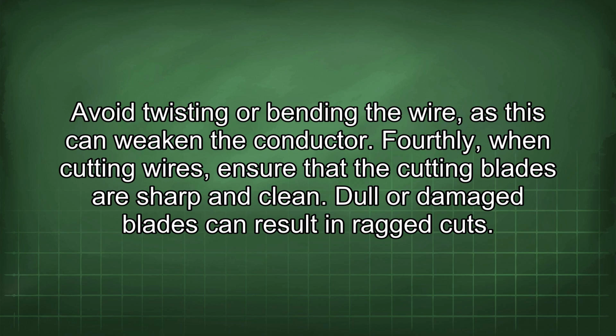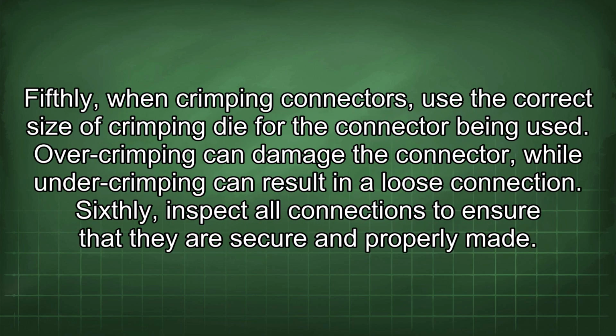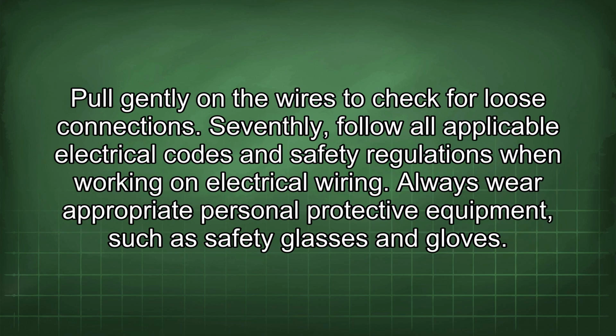Fourthly, when cutting wires, ensure that the cutting blades are sharp and clean. Dull or damaged blades can result in ragged cuts. Fifthly, when crimping connectors, use the correct size of crimping die for the connector being used. Over-crimping can damage the connector, while under-crimping can result in a loose connection. Sixthly, inspect all connections to ensure that they are secure and properly made. Pull gently on the wires to check for loose connections. Seventhly, follow all applicable electrical codes and safety regulations when working on electrical wiring. Always wear appropriate personal protective equipment, such as safety glasses and gloves.